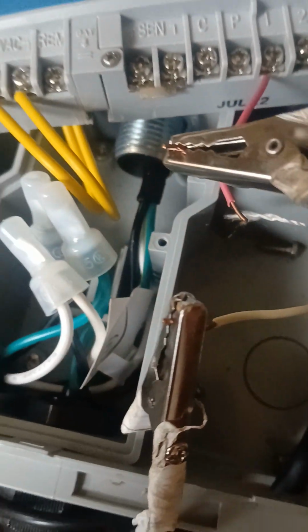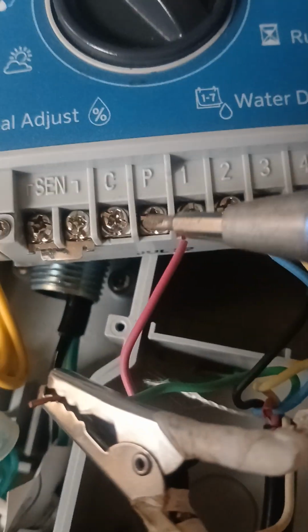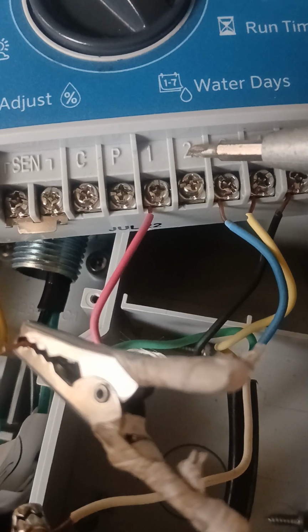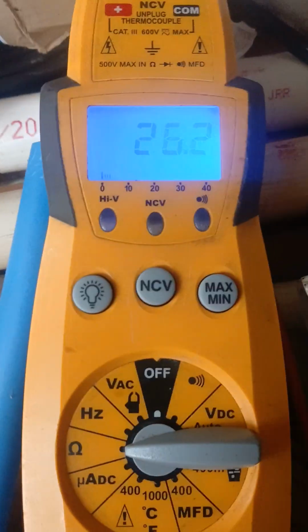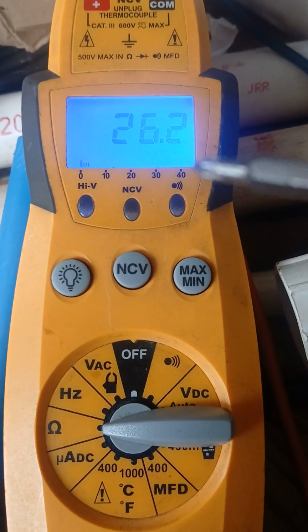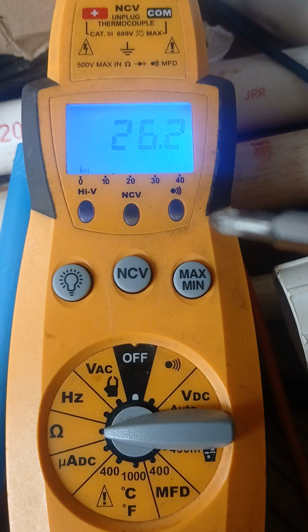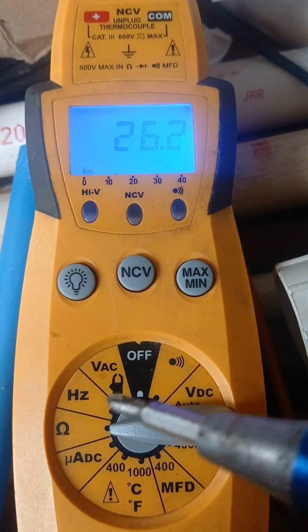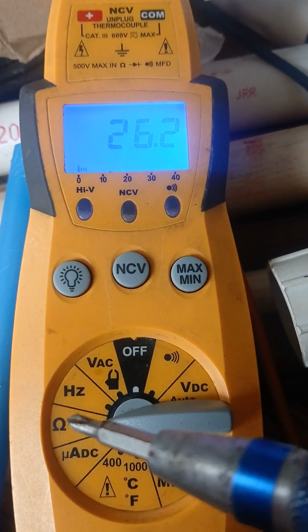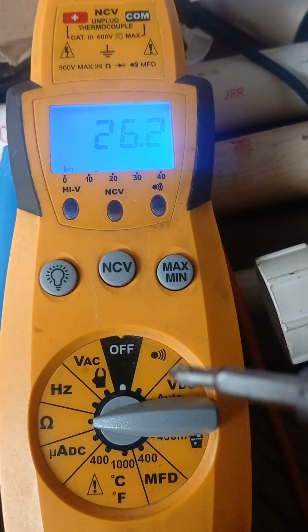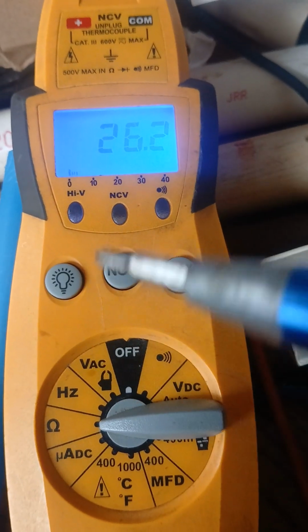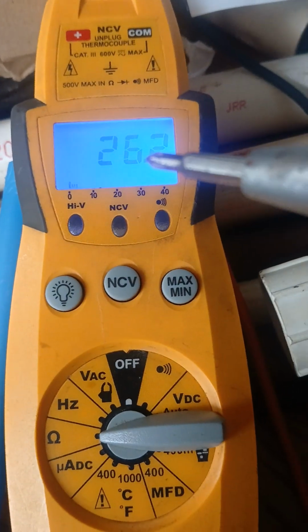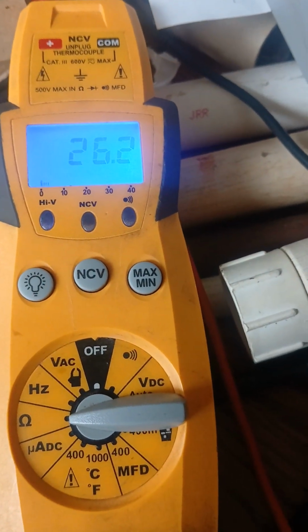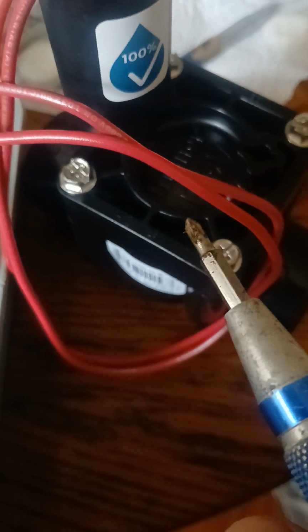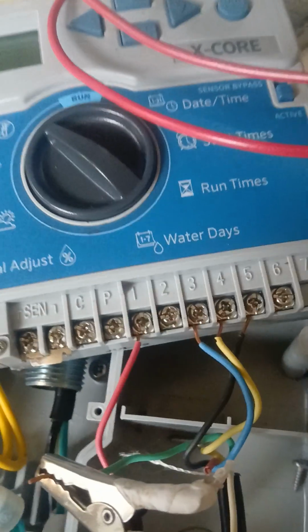We've clipped one wire here after removing the common here and number 2, which is a hot. So therefore, we've actually done this. Then we put the multimeter to the ohms position, this little horseshoe-looking symbol here. When we do this, the meter is reading 26.2 ohms, I think. So anywhere from 20 to 60 is good. Therefore, this valve would test good. The solenoid on this valve would test good.